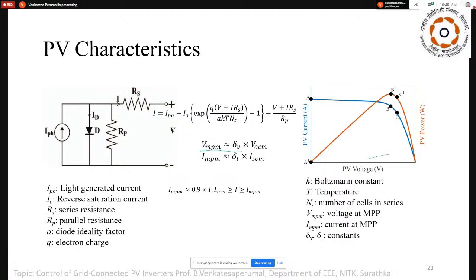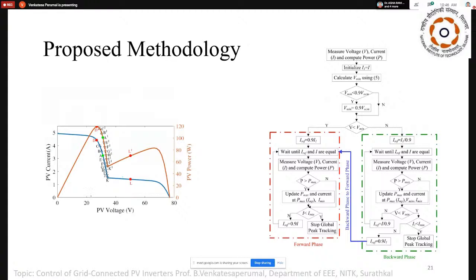One more condition: normally the maximum power point tracking happens at 0.9 times of VOC, similarly 0.9 times of short circuit current for the maximum current. It's a thumb rule kind of thing. In most cases, if you look at the data sheet, you'll find that exactly these points are matching. So this is the normal curve when it is operated.